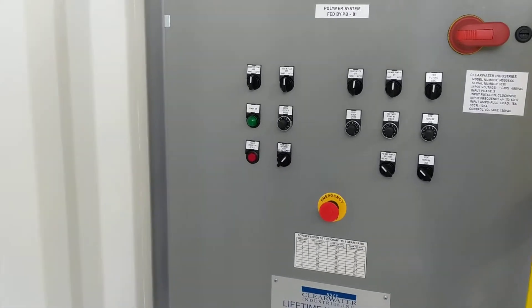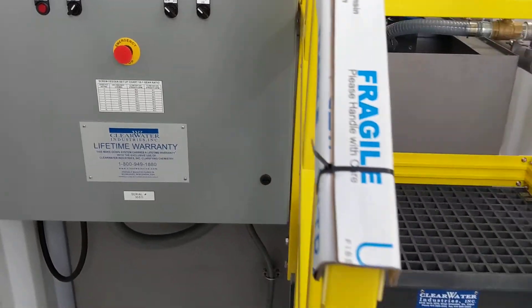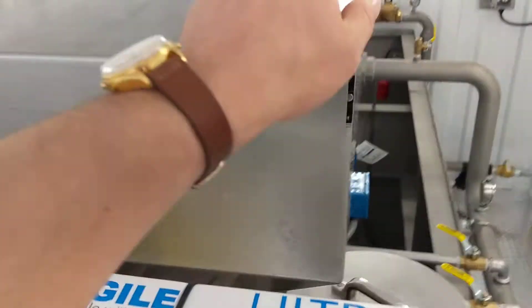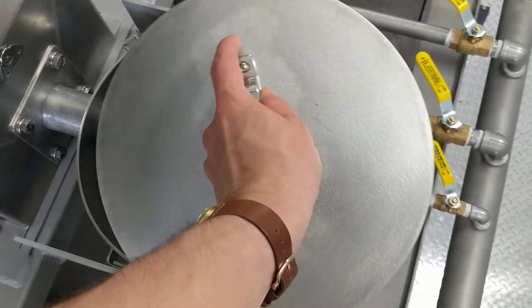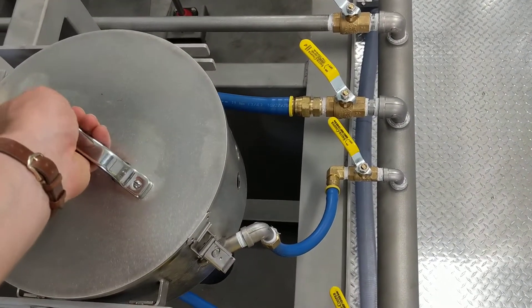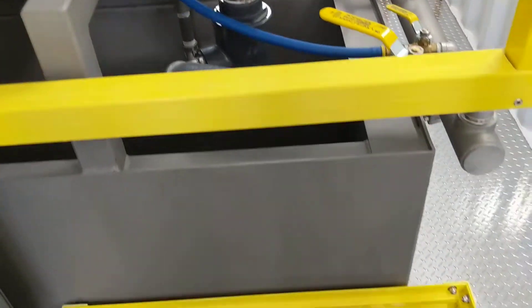This is a Model 500 stainless steel dry polymer system. It uses our analog hand-off-auto controls and is completely automated. We've got a fiberglass staircase going up to a two-bag or 110-pound hopper where the operator loads dry polymer. It's metered into this wetting bowl, where it's first mixed with water, and these ball valves supply flow to additional venturi inductors in the tank to provide 0.25% solution strength of that dry polymer.